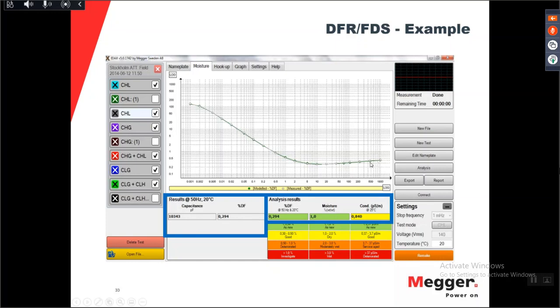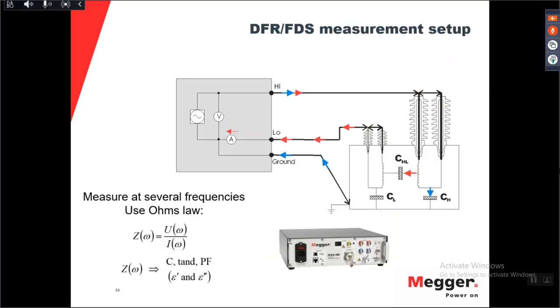Now, as you can see, this frequency measurement actually gives a quite big change in tan delta. It goes from 0.3% to 150%. So it's quite a big range or big span. The measurement method is very simple. It is a voltage source which you apply over the high voltage winding and the low voltage winding. So the voltage applied here gives rise to a current through this capacitance. You measure the voltage and you measure the current, and from that you can actually get the capacitance and tan delta and the power factor as a function of frequency.